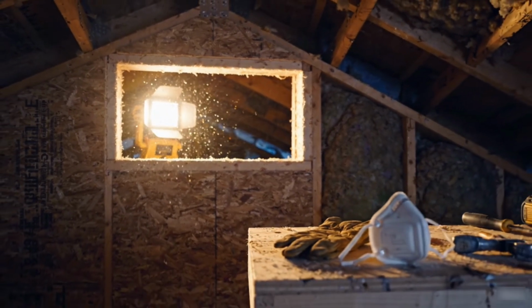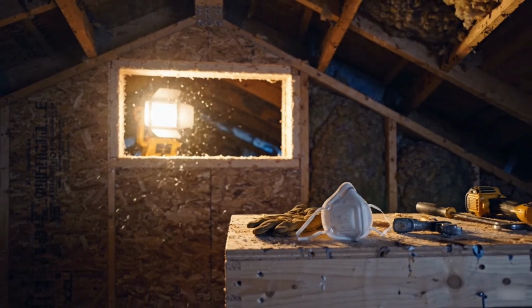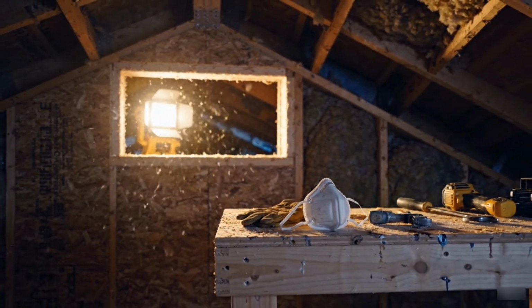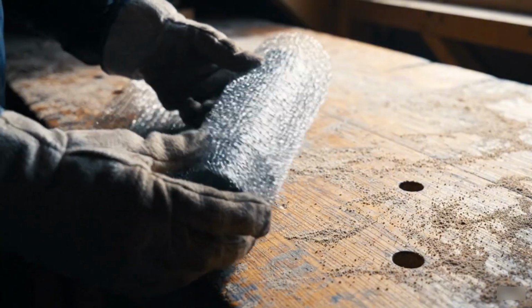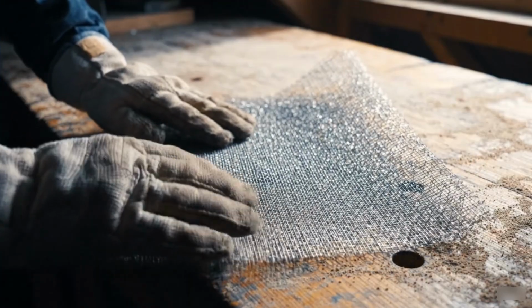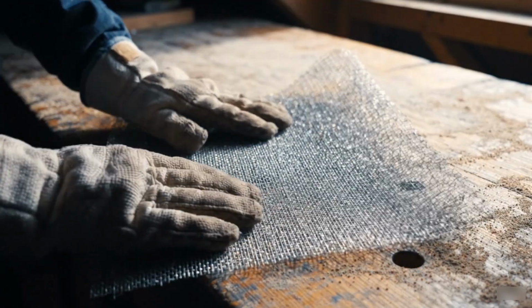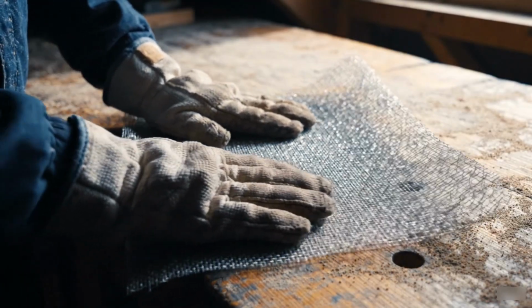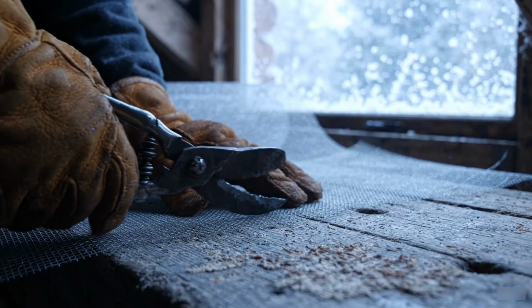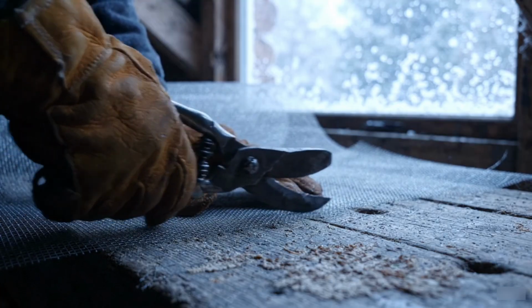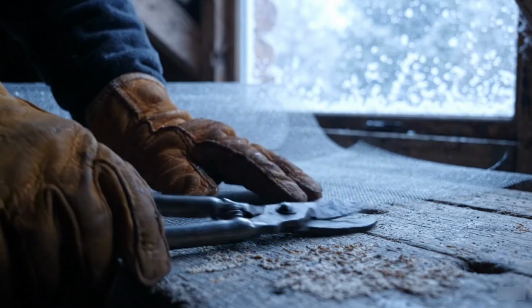If your house has gable vents, they are usually located in the triangular wall section at each end of the attic. Most gable vents installed after 1970 are too small and covered with a fixed louvered screen that blocks more air than it allows. You are going to enlarge the opening and replace the screen. Step 2. Measure the gable vent opening.